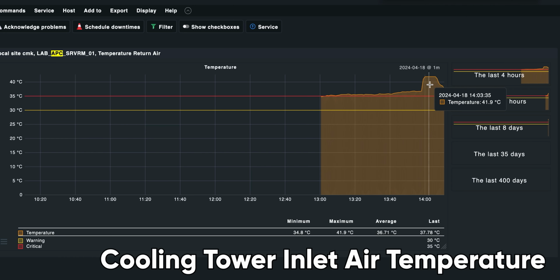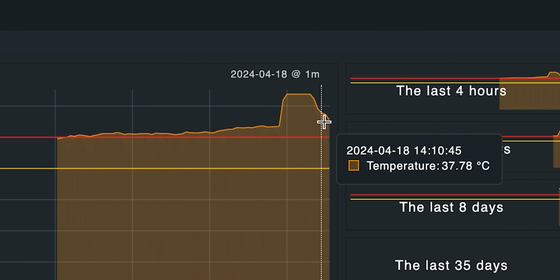I think what I want to see now is if the air conditioner can actually work cooperatively with the heat exchanger, to get it down to like normal temperature in here. Yeah, okay, all right, let's do it. So our baseline is when we started this project, it was hitting about 40 degrees in here with just the air conditioner running. If we can beat that, it means that somehow through the magic of thermodynamics, they are working together. 34 and a half. Plug the goddamn thing back in. Oh, sweet relief. So our peak was 42 with the AC off, and now it's come down to...